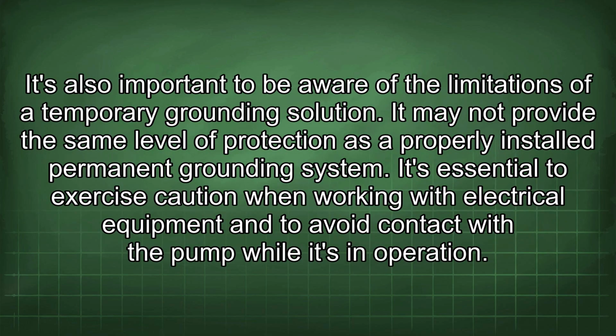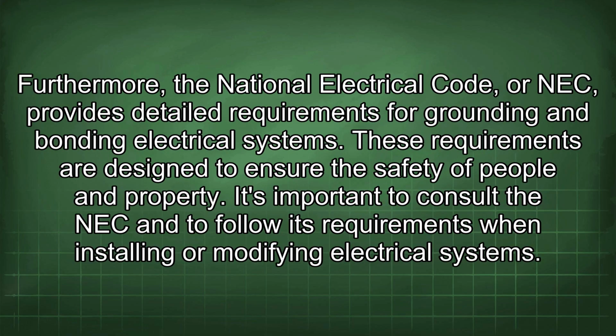It's also important to be aware of the limitations of a temporary grounding solution. It may not provide the same level of protection as a properly installed permanent grounding system. It's essential to exercise caution when working with electrical equipment and to avoid contact with the pump while it's in operation. Furthermore, the National Electrical Code (NEC) provides detailed requirements for grounding and bonding electrical systems. These requirements are designed to ensure the safety of people and property.